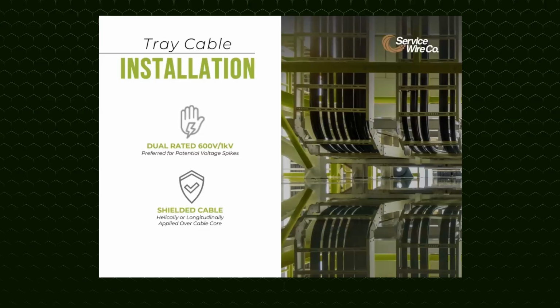For EV projects, you could also use shielded tray cable. Shielding can be applied helically or longitudinally over the cable during the cabling process. Helically applied metallic tape shielding is wrapped around the cable core with a specified overlap to provide 100% coverage. It helps minimize interference from outside disturbances and keeps inside electrical noise from polluting the environment. Longitudinal copper tape shielding is typically applied down the length of the cable with a corrugated metallic tape to provide both flexibility and added physical protection. Helically applied shielding is common for industrial applications, while utility substations more commonly prefer a longitudinally corrugated shield.